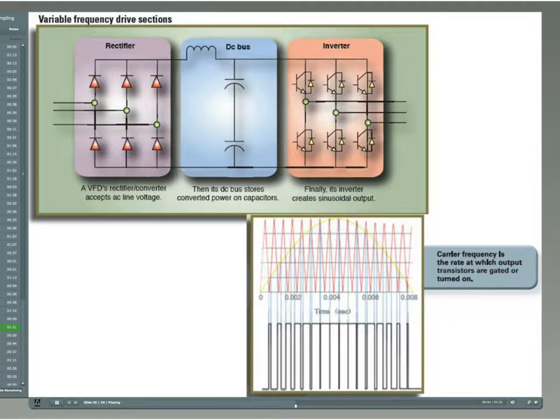Inverter. The third and final primary section of a VFD's main power circuit. The inverter section is comprised of IGBTs that create sinusoidal output current using pulsed DC bus voltage or pulse width modulation, PWM. VFDs themselves are sometimes called inverters, as the presence of an inverter section is the primary difference between VFDs and DC drives. Carrier frequency. In PWM-based VFDs, the rate at which output transistors are gated or turned on, usually 2 to 15 kHz. Higher values yield a better current waveform, but more VFD losses.